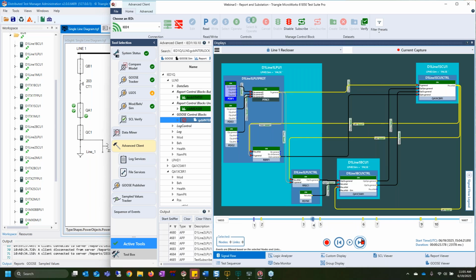And then you can step through each of these individual events that happened and see where the communication is working properly or potentially where it is breaking down. And this will allow you to see how the devices are communicating with each other, despite you being a third party to this as a diagnostic tool.